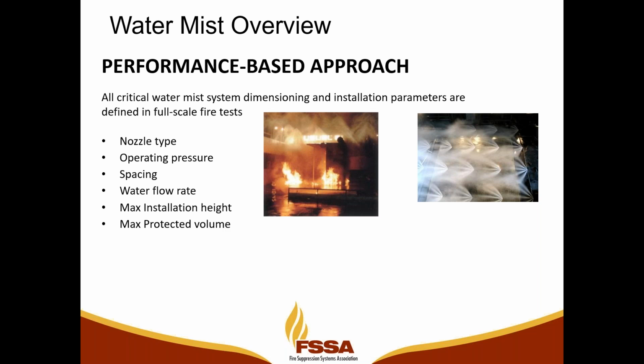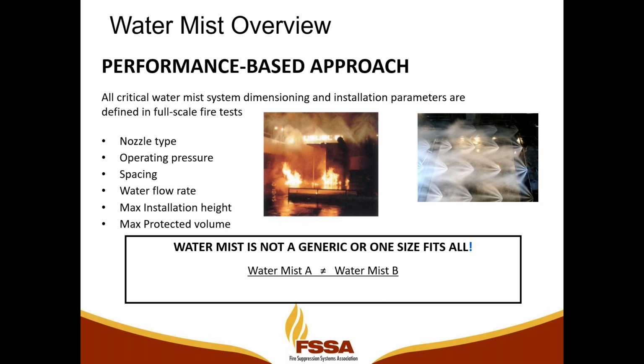And just because one system has a particular listing, or can pass a particular performance-based test, does not mean that every other water mist system can do the same thing. So each manufacturer of water-based systems has to go through their own performance-based testing with FM or through their own fire testing to verify that the system will work on a particular application. Now with FM and UL, they have specific requirements to achieve data center approvals and the various different approvals that they give. Once you gain those approvals, you have passed that performance-based criteria for those types of applications. Next slide. So as I was saying, water mist is not a generic one-size-fits-all. If water mist A passes a test, it doesn't necessarily mean water mist B systems will pass the same test. Next slide.